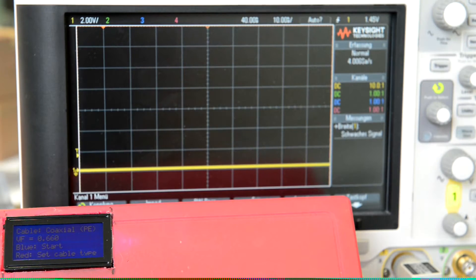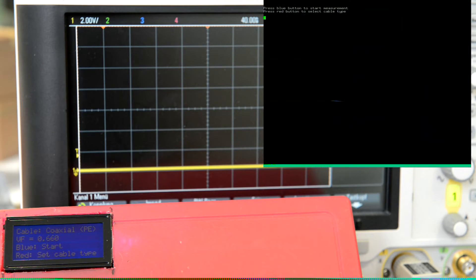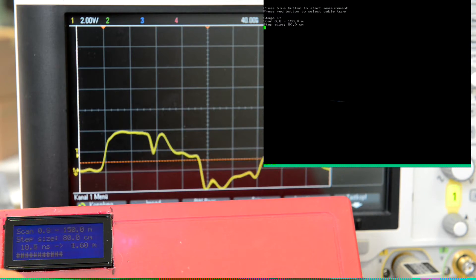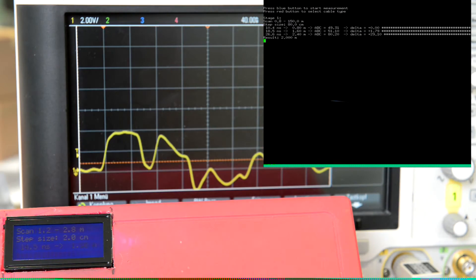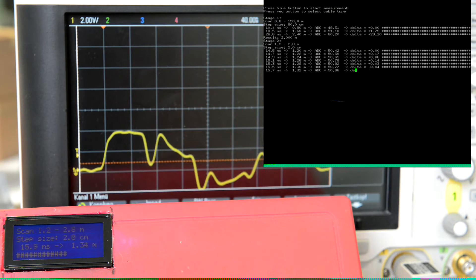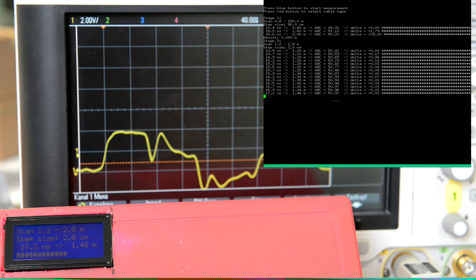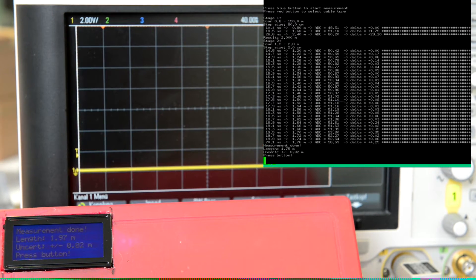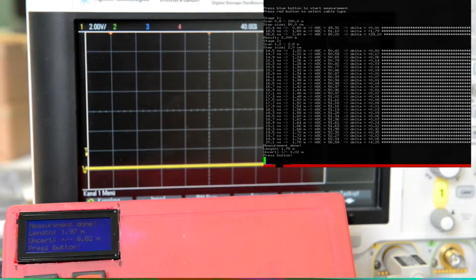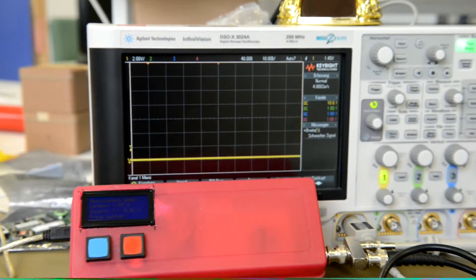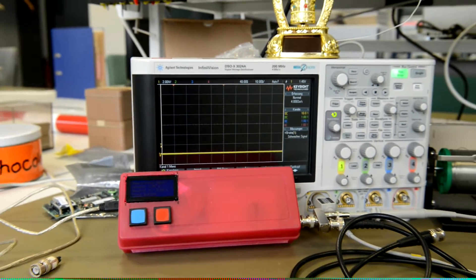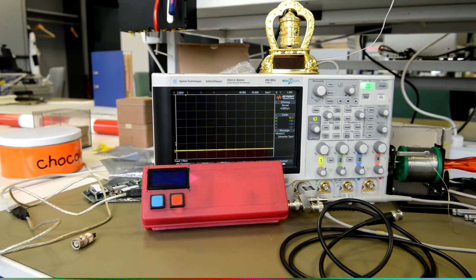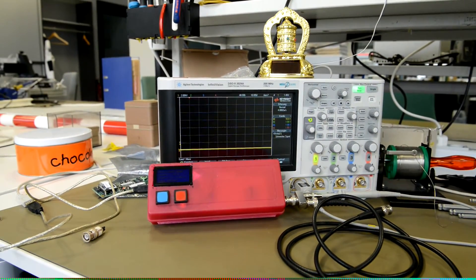This is the automatic two-pass measurement mode. The range of the prototype is only about 10 meters, but the resolution is as small as 4 centimeters. This is very unusual for a TDR. It could even be used to detect if the connector or an adapter at the far end of the cable is mounted correctly.